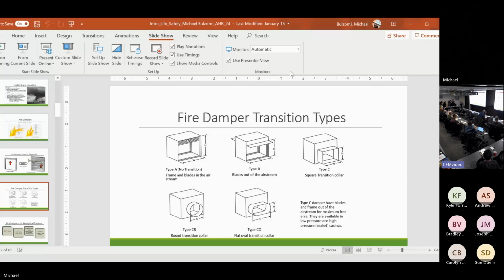To overcome that, I put this transition. We call that a hi-hat, a B type. My damper grows 2 inches in height. I still have a 12 by 12 effective duct opening, but now my damper is 12 by 14. But I have, we'll say conservatively, between 96 and 98% free area on a type B. I wanted 100% free area on a single section curtain damper.